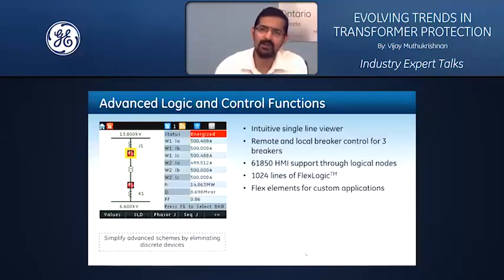But you may also have several other control functionalities. For instance, you want to build a custom logic based on some of the cooling system inputs of the transformer. So you can build some custom FlexLogic in your transformer protection relay to manage that. Up to 1024 lines of FlexLogic, for example, are available in the 845 that you can use for that purpose. You're also bringing in several parameters and measurements like top oil temperature, winding temperature, and so on. When you bring this type of analog input through a DC milliampere or an RTD input, if you have customizable monitoring or protection elements that you can use in the form of FlexElements, as is available in the 845, you can actually build custom applications in your protection relay that can be very powerful and useful in your specific application needs. So that's another aspect.